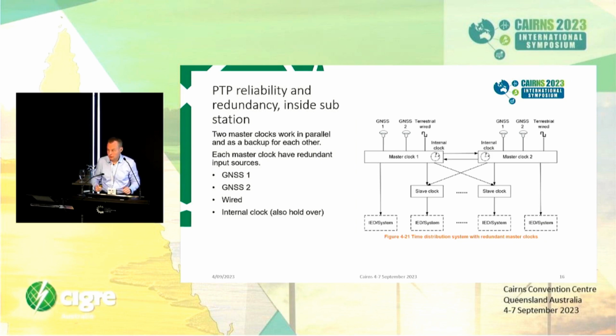If it's totally lost, it's quite easy to detect since we're not receiving anything. It gets tricky when someone can slightly adjust or send a fake signal. These clock devices have algorithms that compare against a reference clock and should detect that the GPS is drifting, that something is wrong. For that kind of situation I talked about secure authenticated Galileo, which can detect when interference sends the wrong messages.